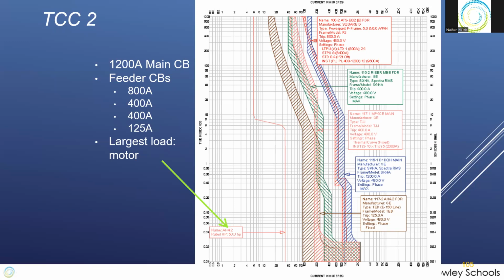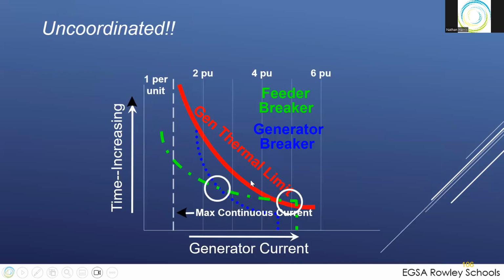Okay? We plot these curves out, determine these settings. We want to watch out for this crossing. It becomes an uncoordinated system. And that analogy would be you have a fault down a feeder breaker, but instead of tripping that feeder breaker, you trip out the generator main breaker. You don't want that, obviously.